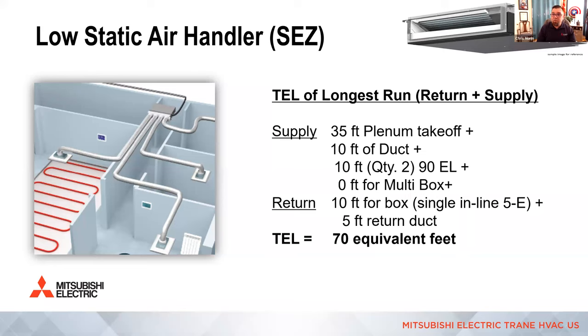Now, when we do this equivalent length value math, we're only doing the longest run. So on the supply side, in this example, that first fitting off the end of the box is 35 feet. And you would see that on your duct calculator on the back, typically on the top left, shows you plenum fittings. And you're gonna look for the ones that are straight or tapered and get the value off of that, all right? So even though it's only 6 inches in actual feet, it's actually a 35-foot fitting because the air has to make this pressurized turn or reduction.